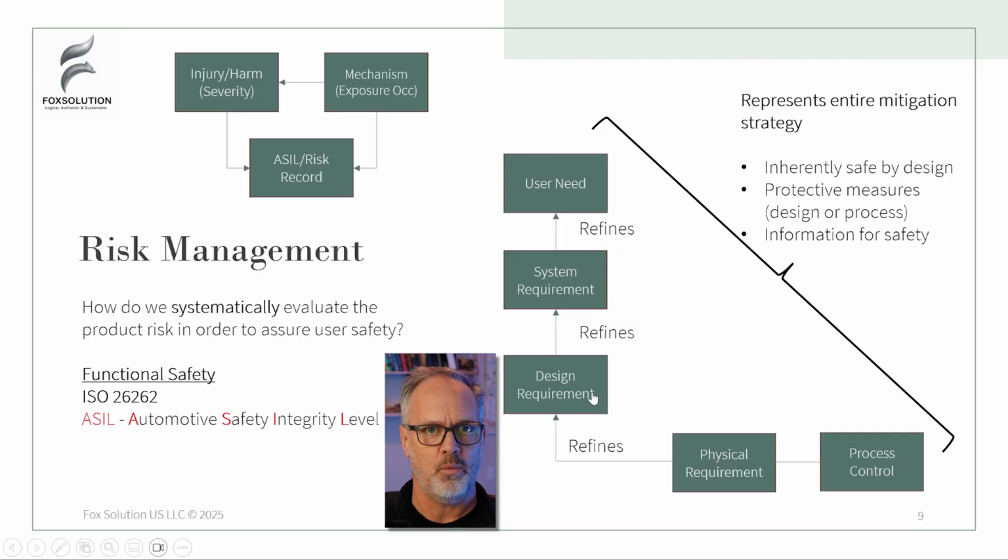That's one of the ways that people evaluate user risk. Or ISO 14971 for medical device discusses this as a risk to users based on hazardous situations and harms. So the terminology is different, but essentially what we're doing is the same. We're just evaluating what is the end risk and what is the severity of the injury that could result as part of that. And as part of that, when we do the calculation, we're going to identify how bad is this particular problem.